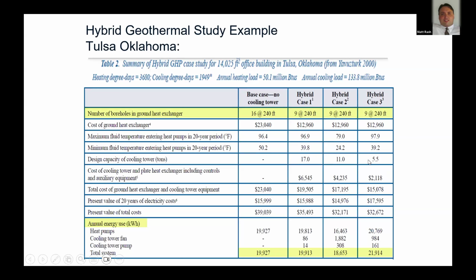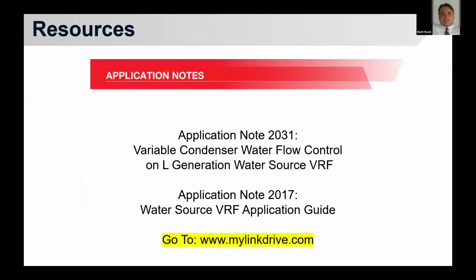You've got the added cost of the towers, but generally that's dwarfed by the cost of the additional wells. So a hybrid strategy can bring the cost of these systems down and really optimize their effectiveness. The goal should be to have a balanced well field, dumping just enough heat into it for what you need to take out for winter operation, keeping it balanced and doing that efficiently while optimizing upfront cost. That's a lot in a short period.